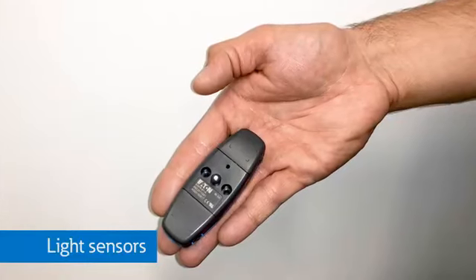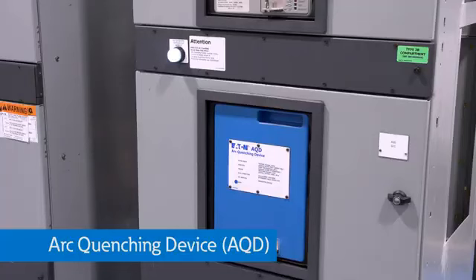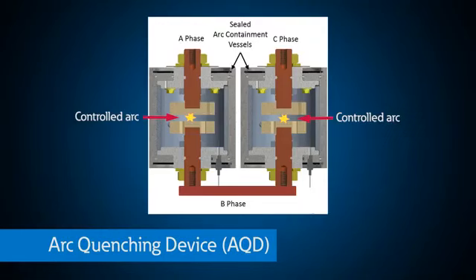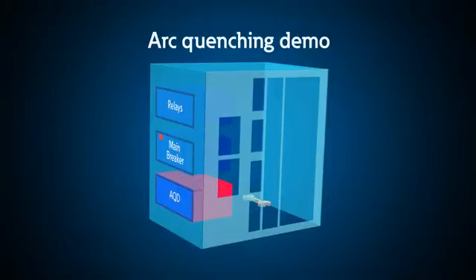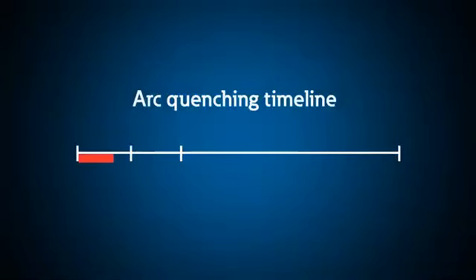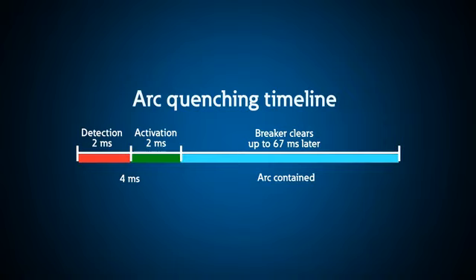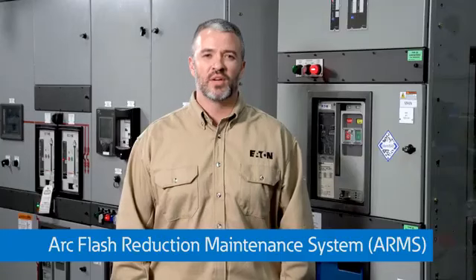Basically, arc quenching switchgear uses a system of light sensors, current sensors, and this device to create a parallel arc during an uncontrolled arc in the switchgear to provide an alternate and controlled path for fault current until an upstream device can clear the fault. During this scenario, your people and equipment are protected because the arc quenching switchgear reacts so fast and responds before the dangerous pressure wave builds up. With this demonstration, we can show you exactly how arc quenching switchgear works.